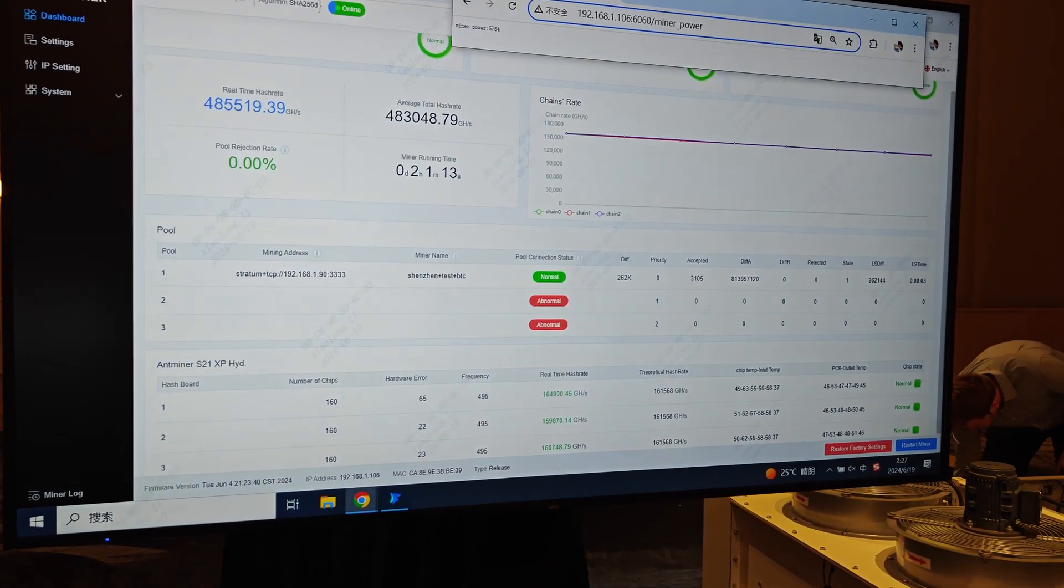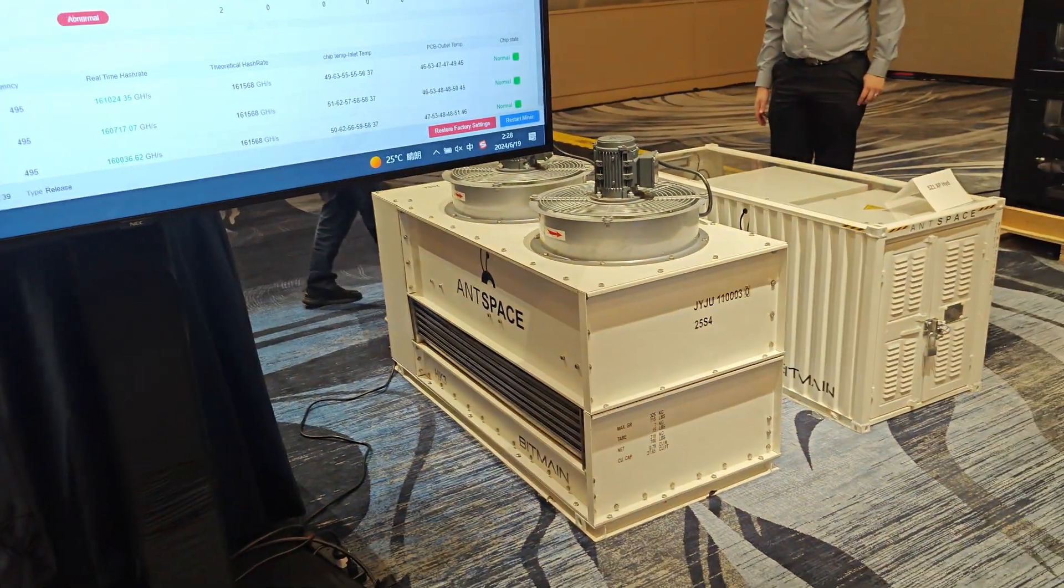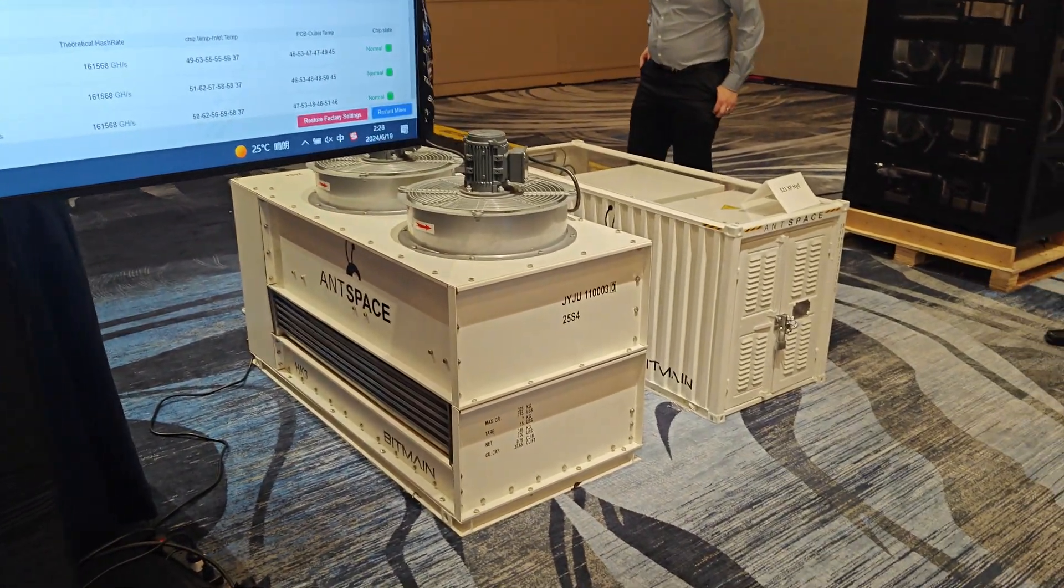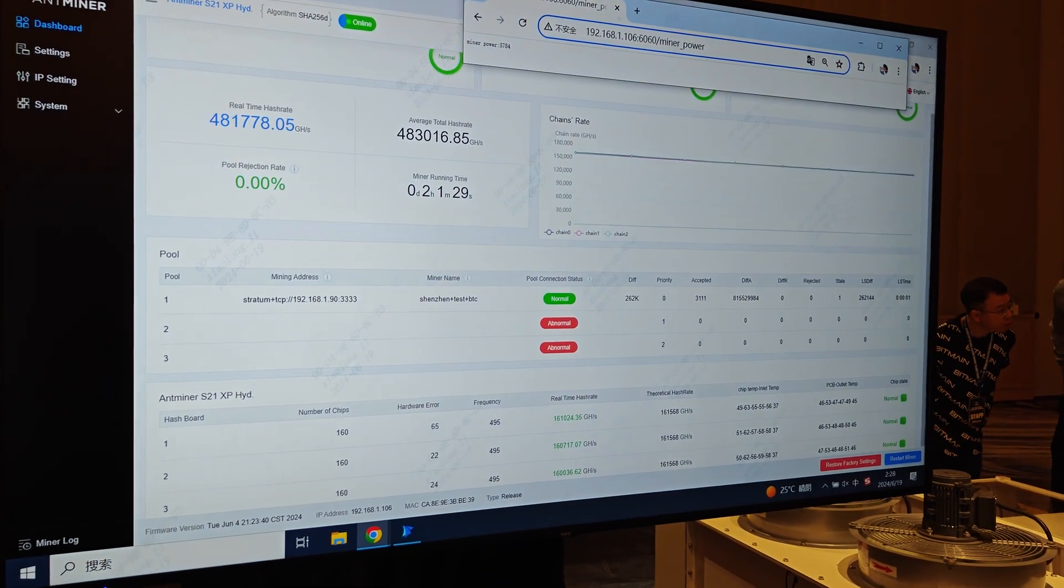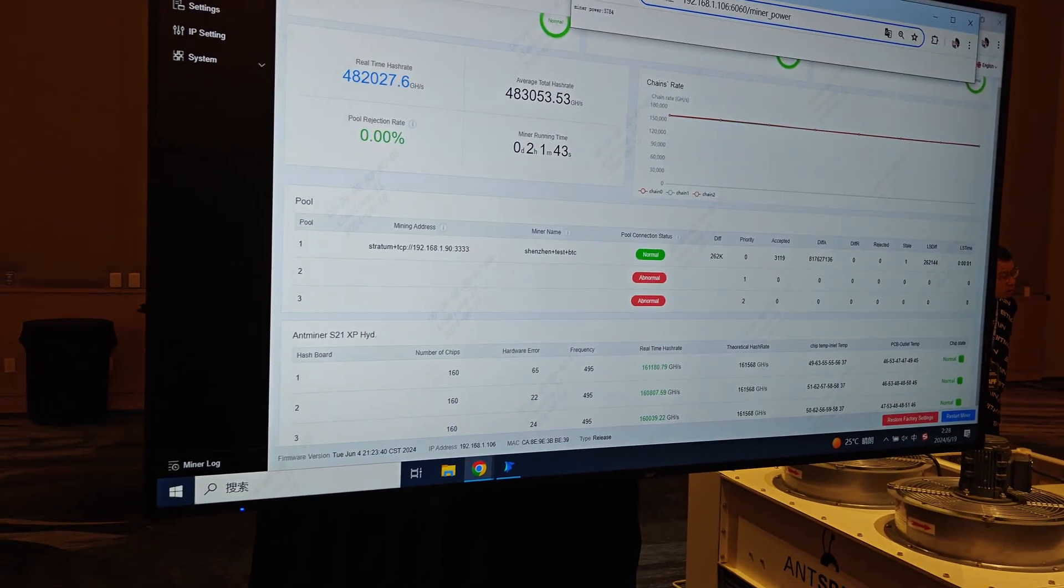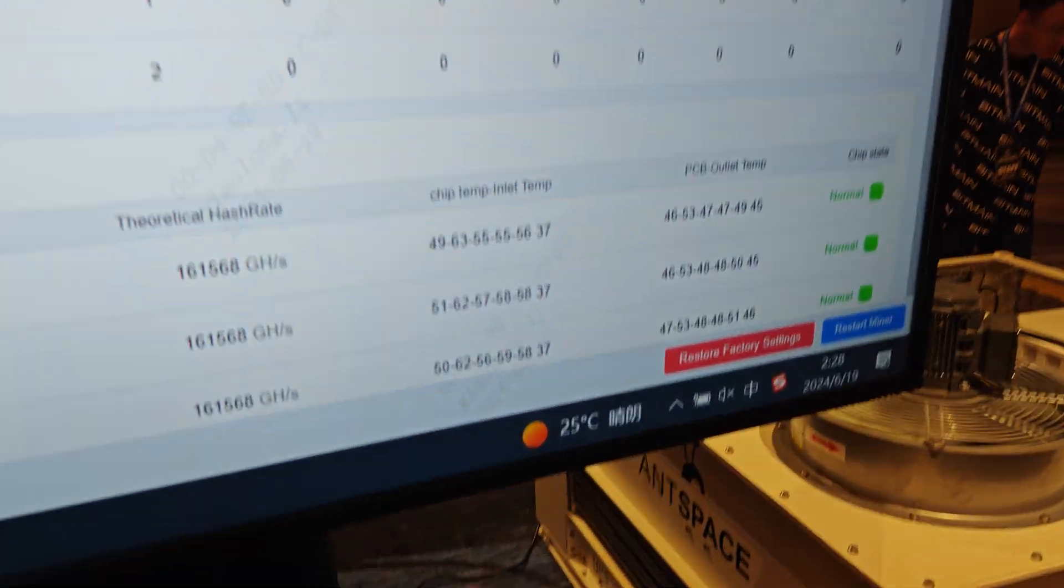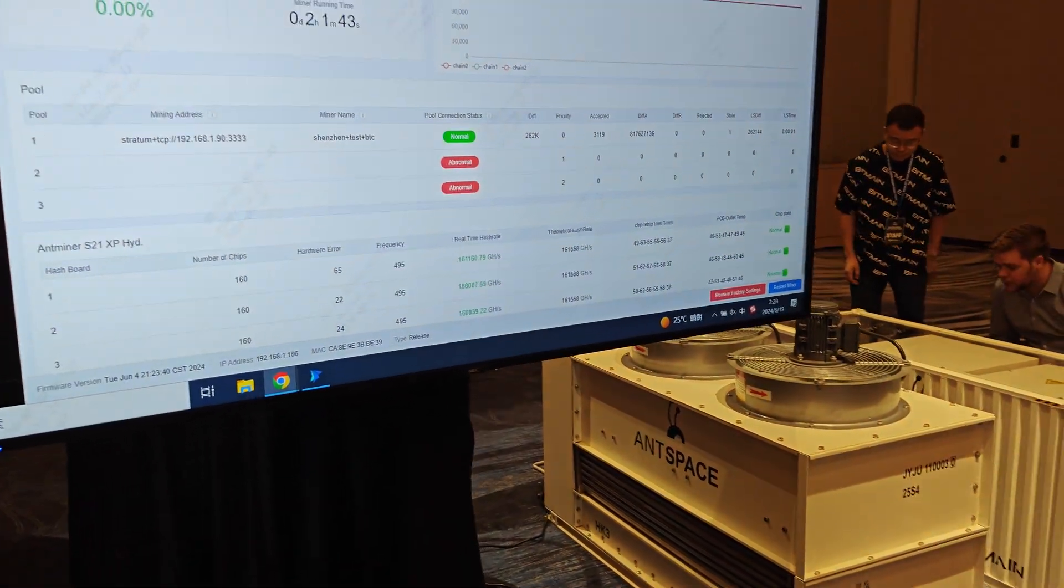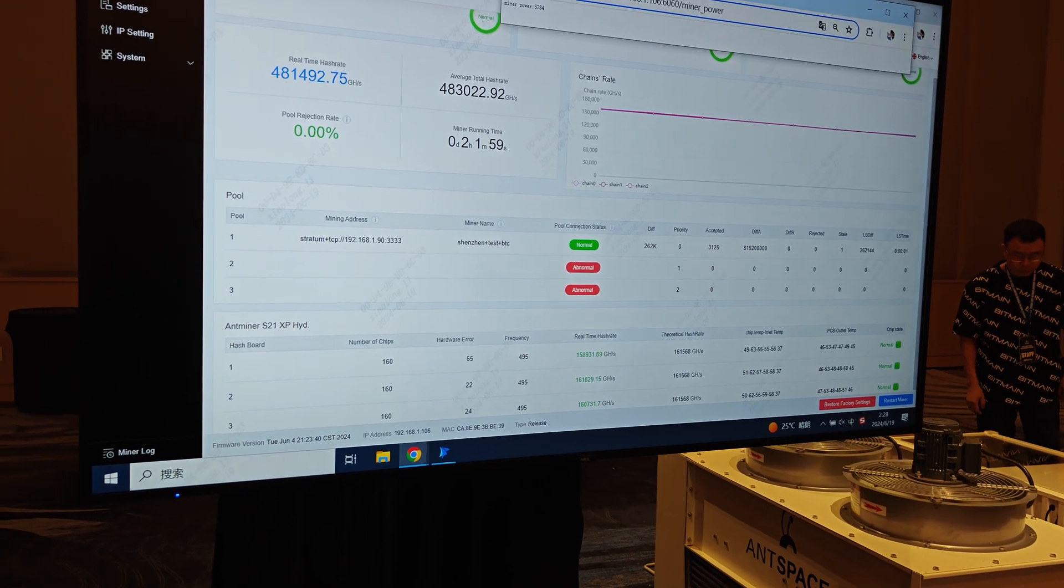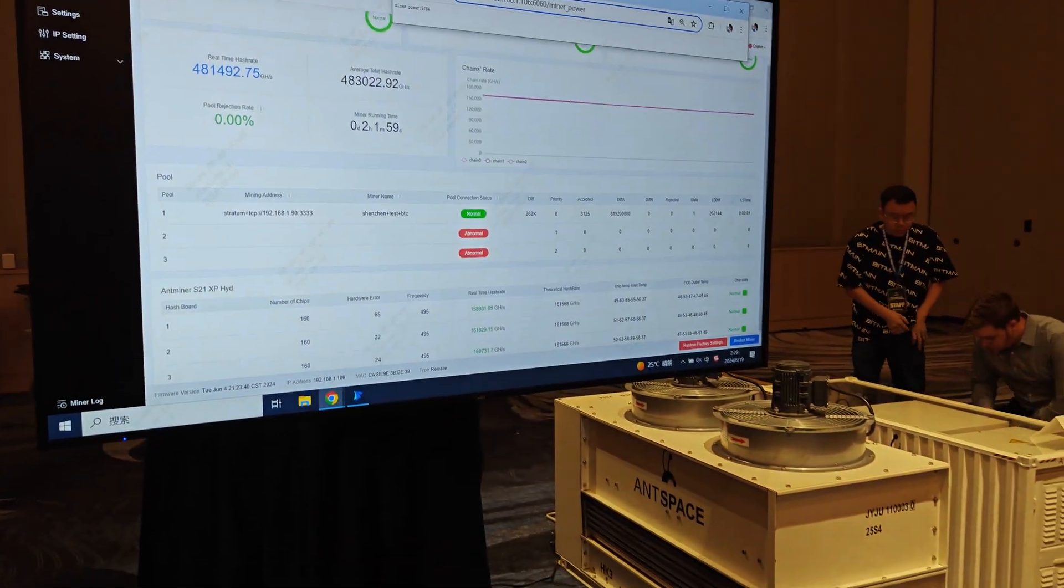But if you do go higher than that, let's say you have a day when it's 100 degrees outside, and you are on a closed loop. Now, on an open loop, you're just going to be consuming water. You're going to be consuming six gallons a minute on water. But if you're on two closed loops, then when your ambient temperature is about 100 outside, your inlet temperature is going to go past that 35 mark for maximum efficiency. Because you're not cooling fast enough as the temperature outside has gone up.